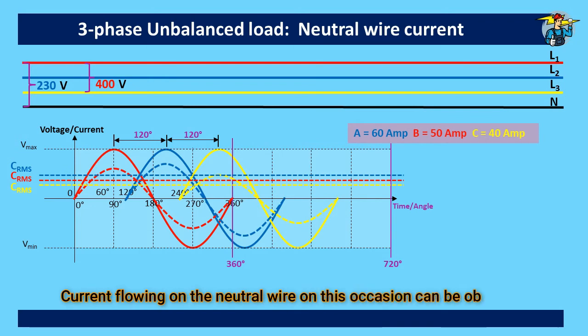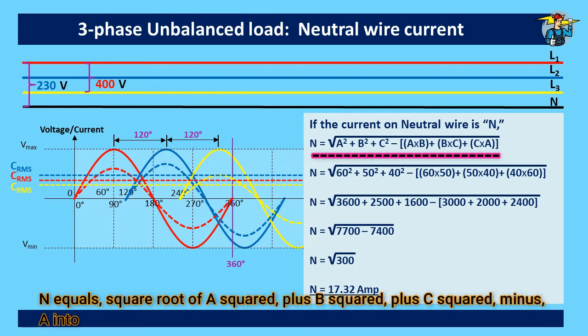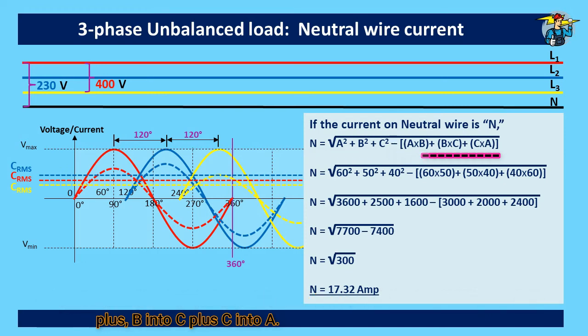Current flowing on the neutral wire on this occasion can be obtained from the given equation: N equals square root of A squared plus B squared plus C squared minus A into B plus B into C plus C into A.